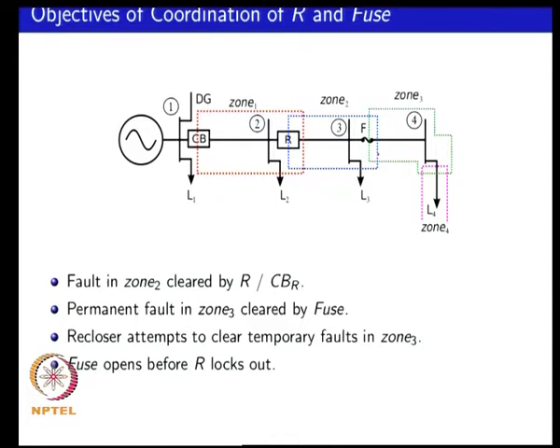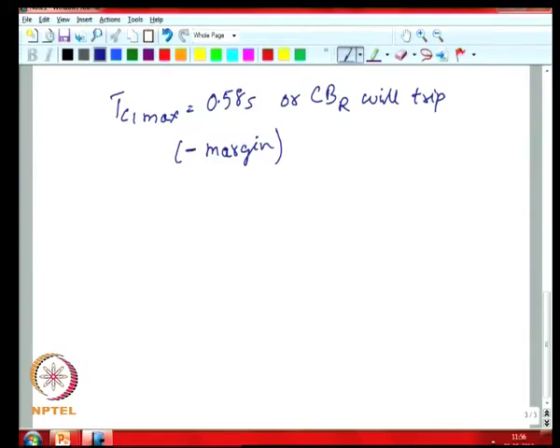Looking at what the Tc durations should be for this particular condition: if you make the time duration too small, there is a chance that the fuse will not blow and the recloser would lock open. You want the durations to be larger in this case, so as to ensure that the fuse blows for a permanent fault before the recloser locks out.